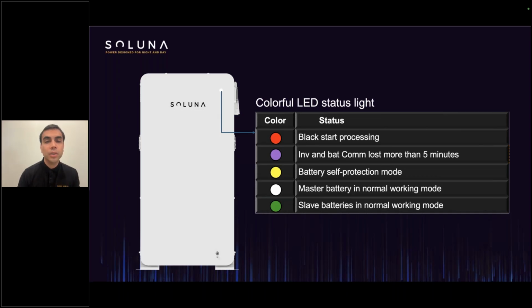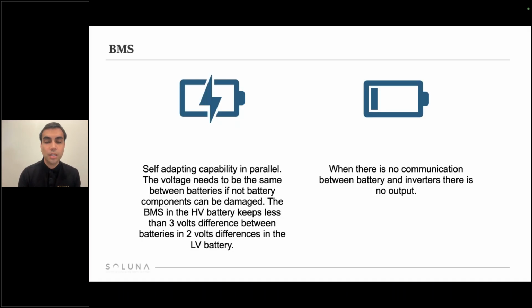So the red light will turn on when you press the black start. The LED on the batteries will turn red for 10 seconds, and then it will go back to the status, whatever the status might be. In the inverter and the battery communication, if they lost more than 5 minutes of communication, let's say that there is a blackout, there is no PV or grid coming in, and the inverter is off, but you have juice in your battery, you can use that energy within the battery to power the inverter back on with the black start button, and it will allow for communication again with the inverter, so that we can monitor any issue that there may be.